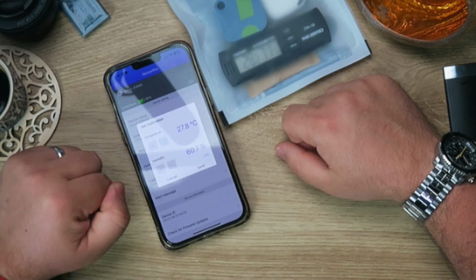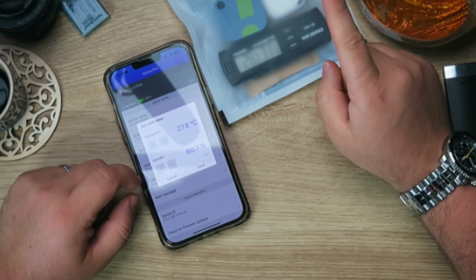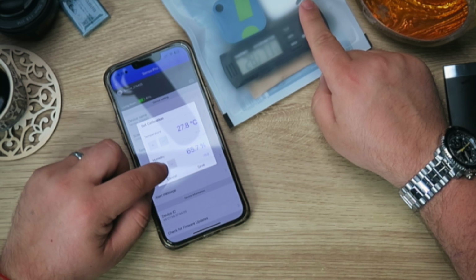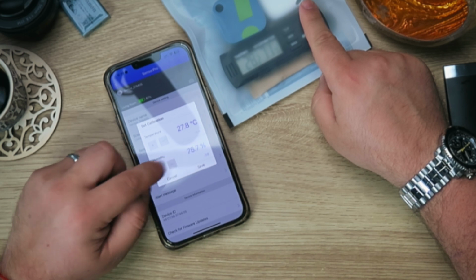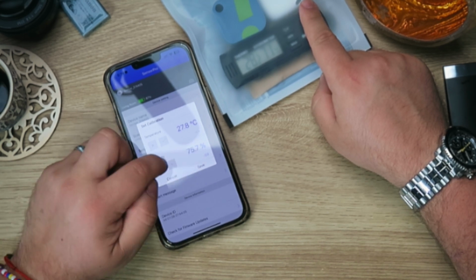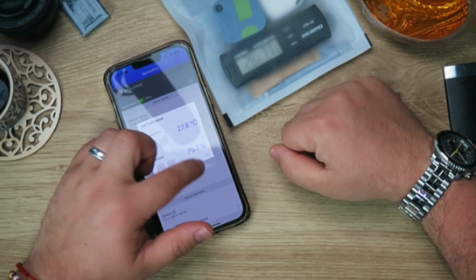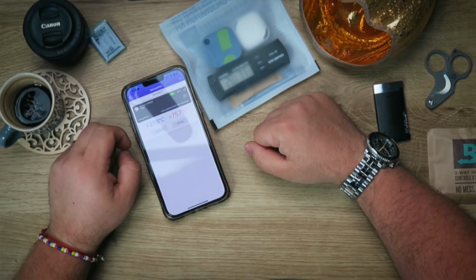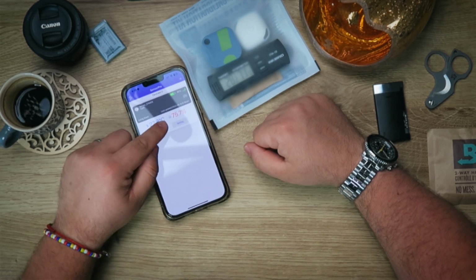Anyway, back to the hygrometer. You go into settings, calibration, so it should be reading 75. All we have to do is just increase it to 75, and there you go. Forget the 0.7 because that's gonna change a little bit.